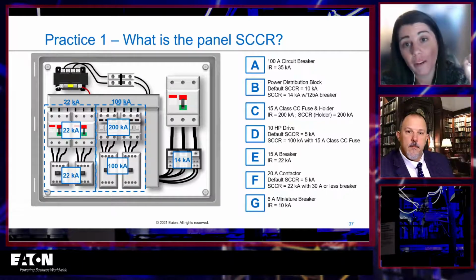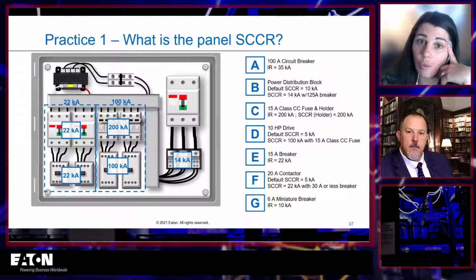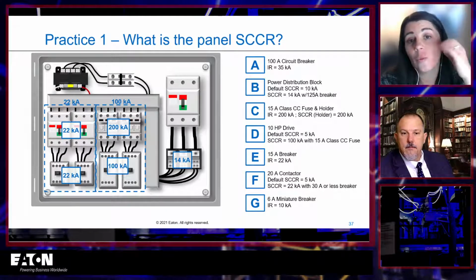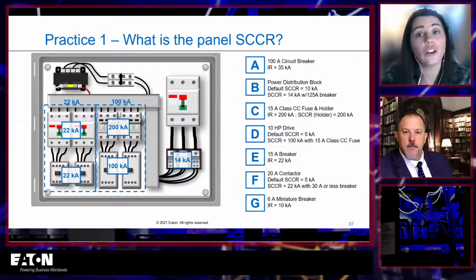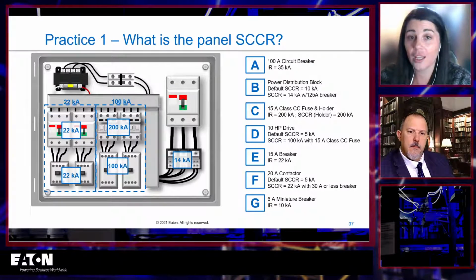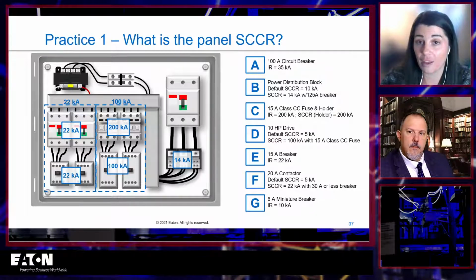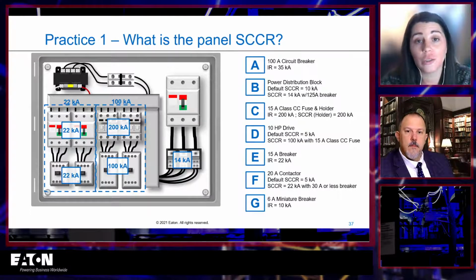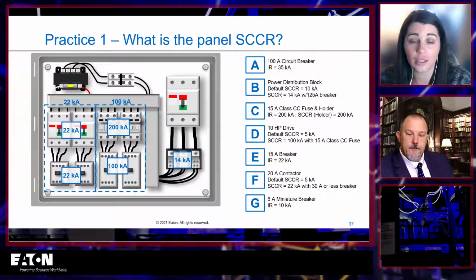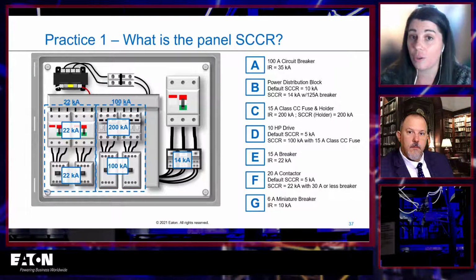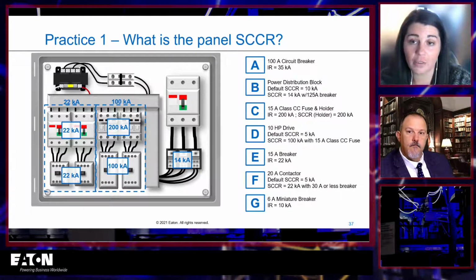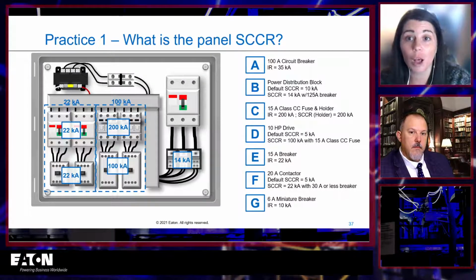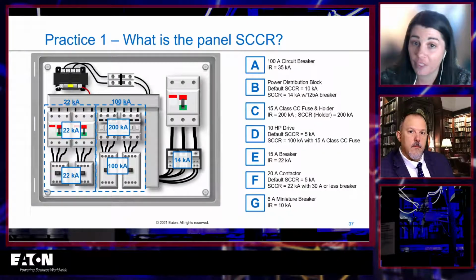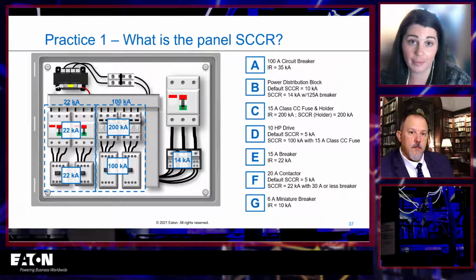Now I'm going to look and see it's being fed from a 100 amp breaker. So now, am I at the default, or do I get to use the high one? We get to use the high fault rating, and that's because when I look up the short circuit current rating of components, that is a maximum amp rating of an upstream device. I'm always allowed to use a smaller device in front of it. A smaller device is going to, if anything, open faster and protect you better. So it's considered a better protective device, and you can use that instead. So B, even though it says 14 kA with a 125 amp breaker, I'm using a 100 amp breaker. That's okay. Smaller is okay. If I were using a 150 amp breaker, no go, I'd be back down to 10.